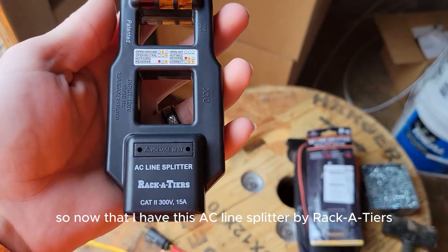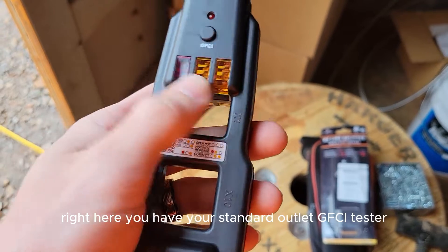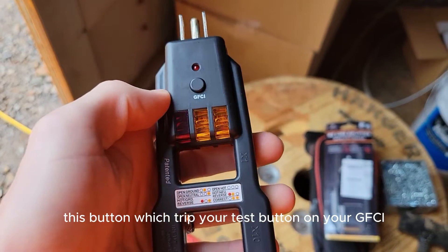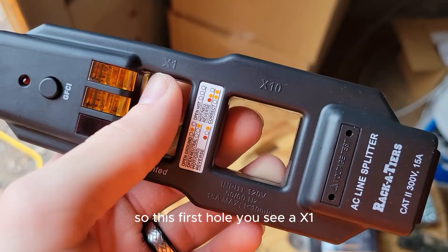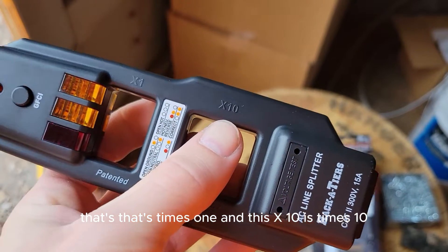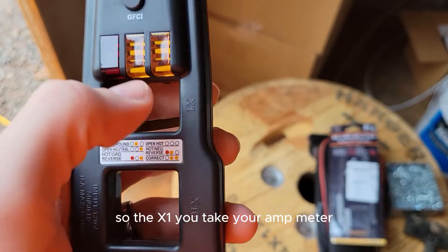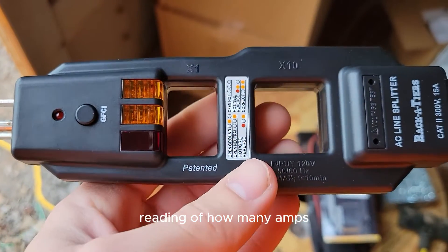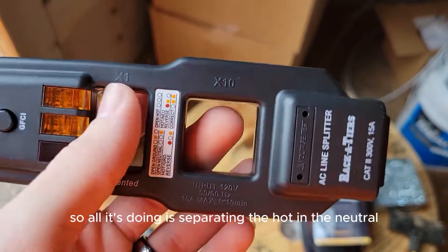Now that I have this AC line splitter by Rack-A-Tiers open and out of the box, I want to show you the functions. You have your standard outlet GFCI tester, a test button to trip your GFCI, and a chart showing correct wiring. These two holes here are a big factor — the first hole is x1 (times one), and the x10 hole is times 10. You wrap your amp clamp around x1 for the true reading of how many amps whatever you plug in is pulling — it's just separating the hot and neutral.